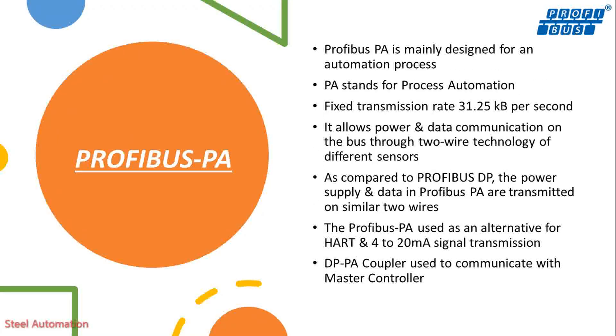Profibus PA is mainly designed for automation processes. PA stands for Process Automation. It operates at a fixed transmission rate of 31.25 kbps. It allows power and data communication on the bus through two-wire technology for different sensors. As compared to Profibus DP, the power supply and data in Profibus PA are transmitted on the same two wires. Profibus PA is used as an alternative to HART and 4 to 20 mA signal transmission.